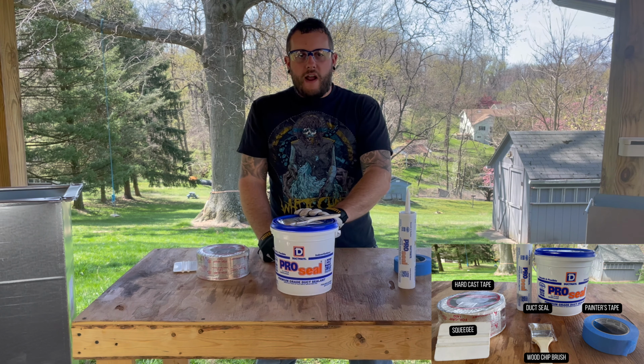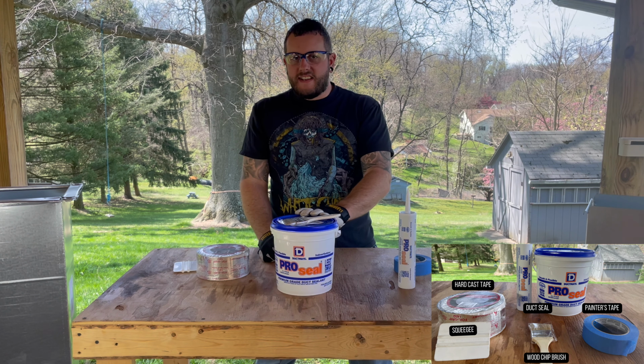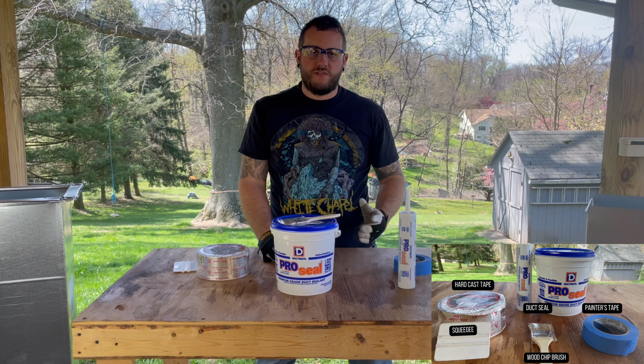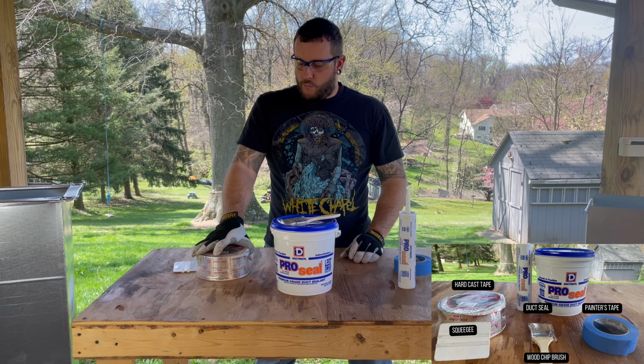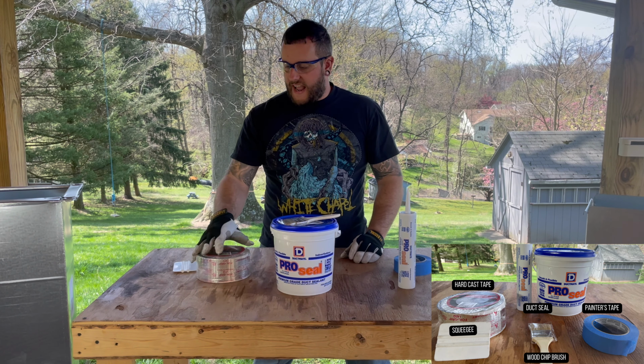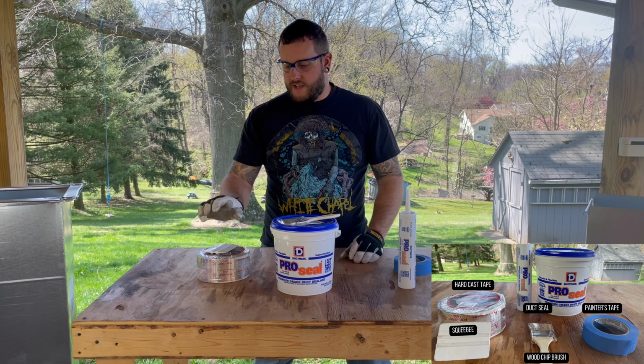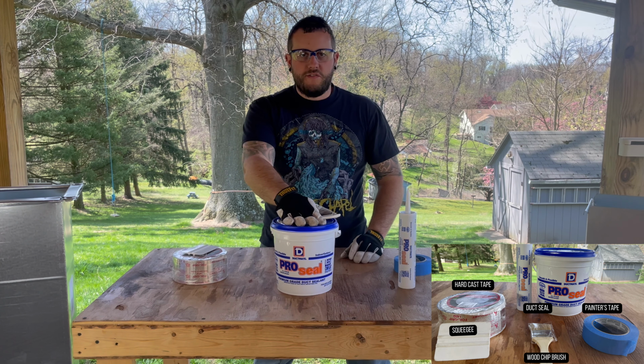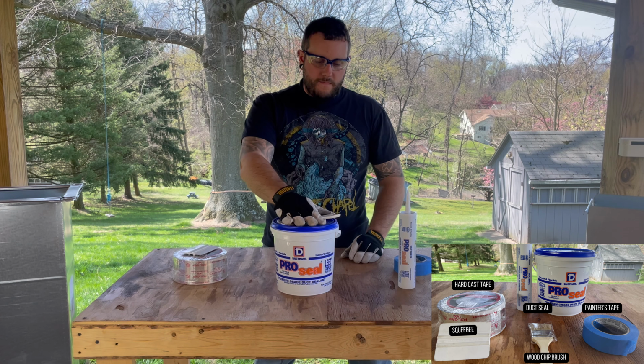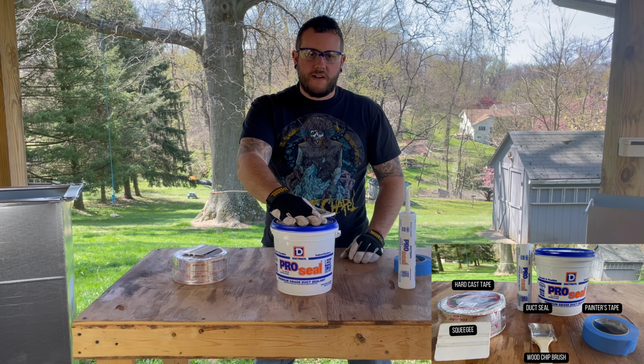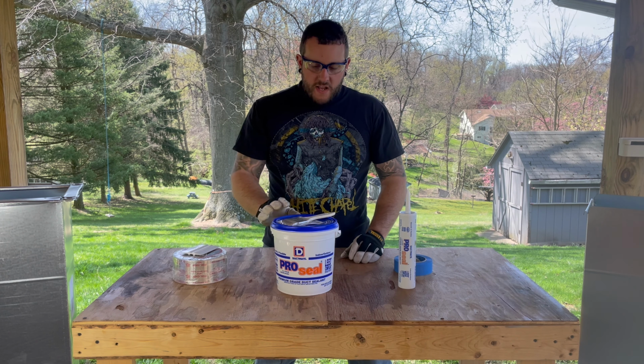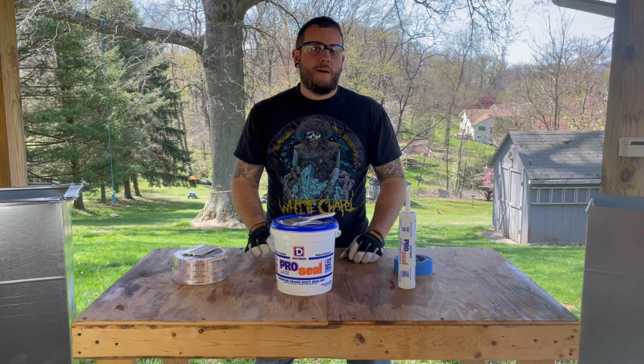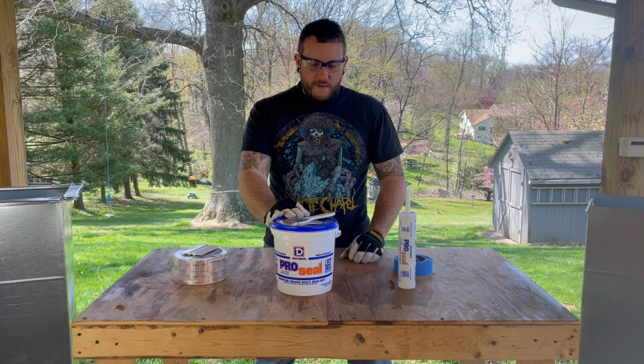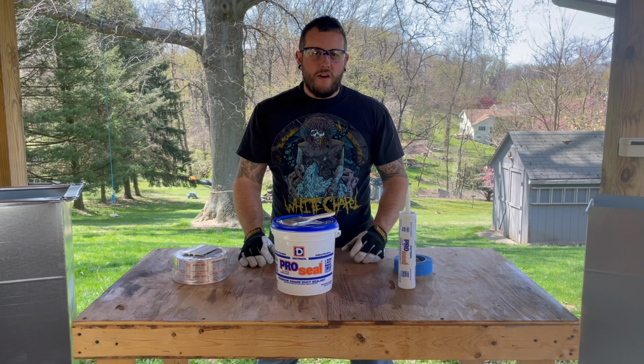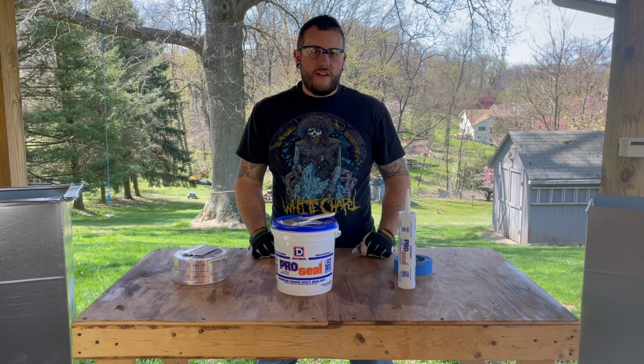And if we have to seal ductwork outside of ideal weather conditions, and we'll go over what some of those weather conditions are, we can use hard cast tape and put it on with a squeegee, but we want to be using duct seal as our first line of defense when it comes to sealing ductwork. Duct seal, I will say, does not come out of your clothes. So one of the most important things is that you don't wear your favorite band t-shirt when you're getting ready to duct seal.